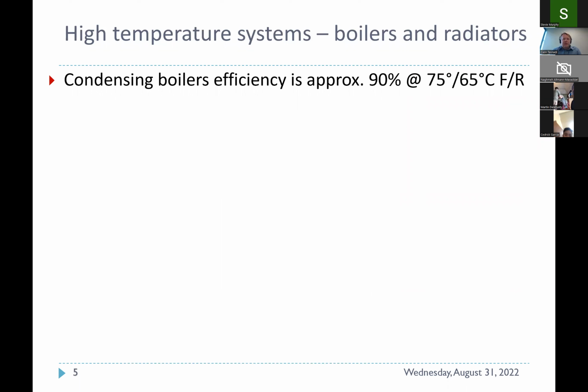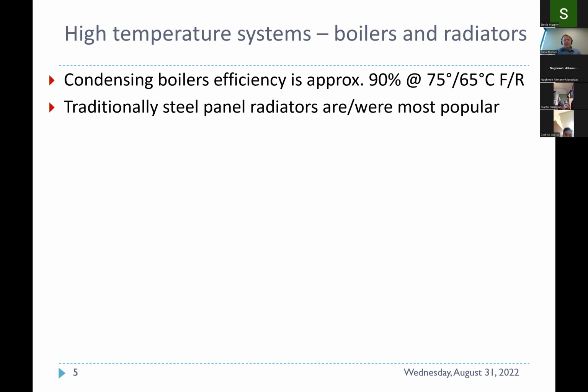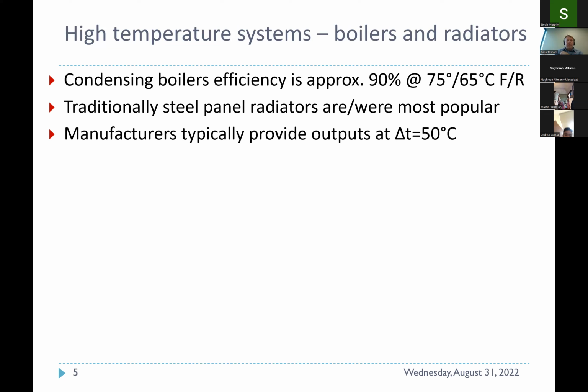Looking at existing high temperature systems, existing or new, typically what we use for this is condensing boilers, which will have an efficiency of approximately 90%. And typically we have them working at 75, 65. Boilers will work best in condensing mode when we deliver 45 degrees, but typically that's what's out there, 75 over 65 flow and return. Traditionally, steel panel radiators are the most popular and have been used with boilers. And radiator manufacturers will typically provide outputs for the radiators at a delta T50.